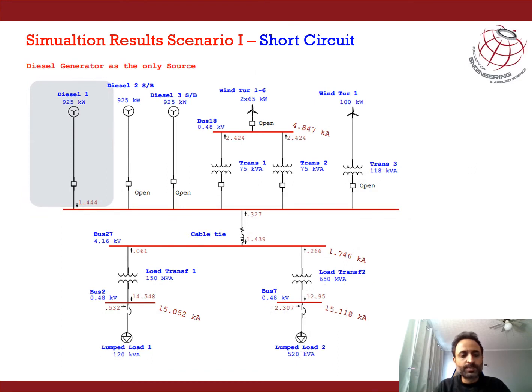If we consider the same case for short circuit studies, we found that since the diesel generator is the only source, about 1.444 kilo ampere, that is 1444 ampere of short circuit current, is fed by the diesel generators into the bus. The fault current, as expected, on the secondary side of the load transformer has increased because the voltage level is lower at the load end. So this increases to 15 kilo ampere. However, these results are also within the expected parameters, because in industry we are able to get switchgears of 25 kilo ampere and more. So these results are also within the limit. So we can conclude that for scenario 1, both the load flow and short circuit studies were successful and within the expected parameters.